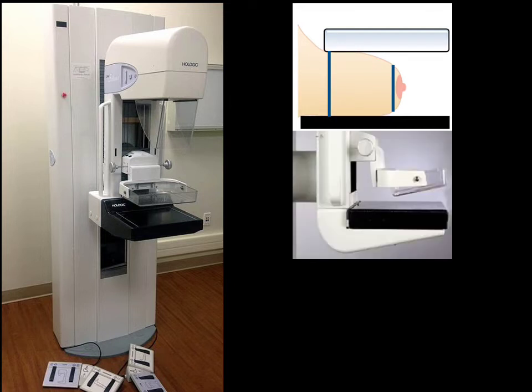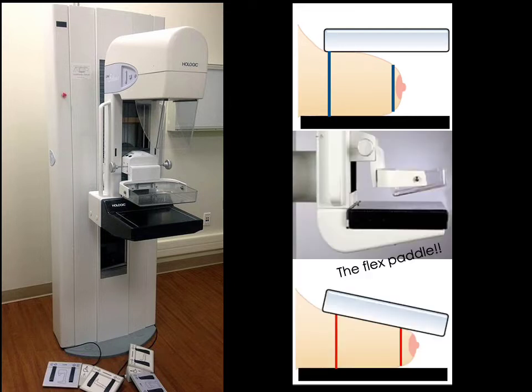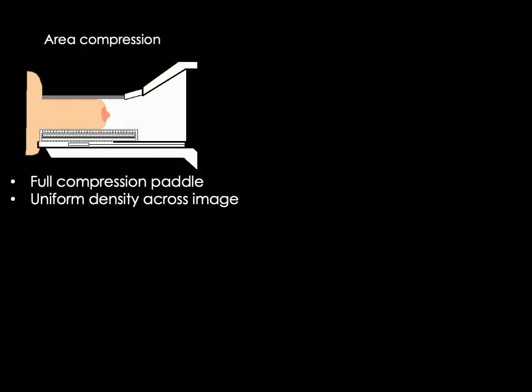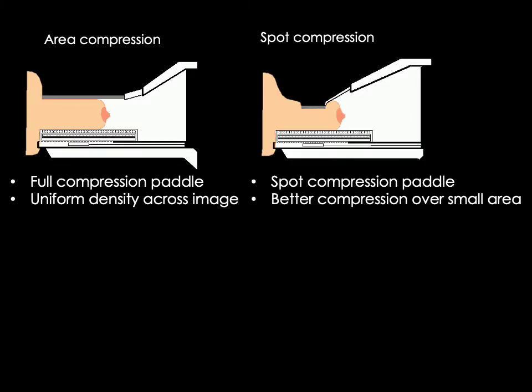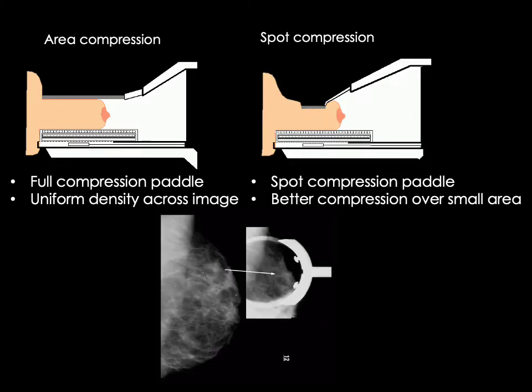These days, most mammography systems use some sort of flex paddle design. Instead of having the paddle stay parallel to the image detector, it can bend slightly to allow adequate compression of the nipple side of the breast. Another technique is spot compression, used to improve image quality over a small area of the breast — typically to zero in on something that may not be clear in the standard view acquired using the full compression paddle.